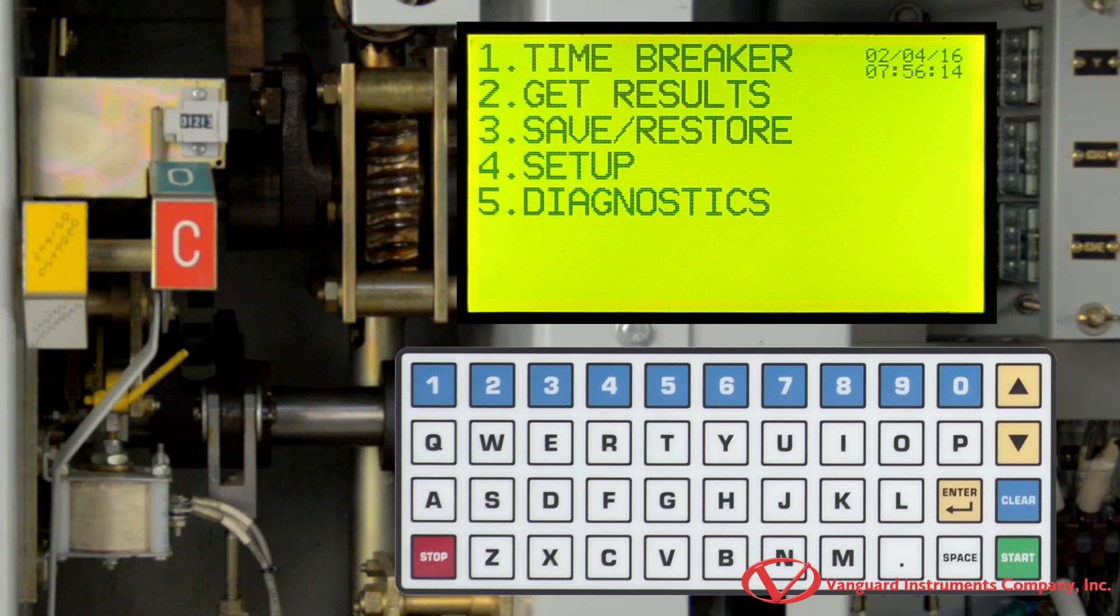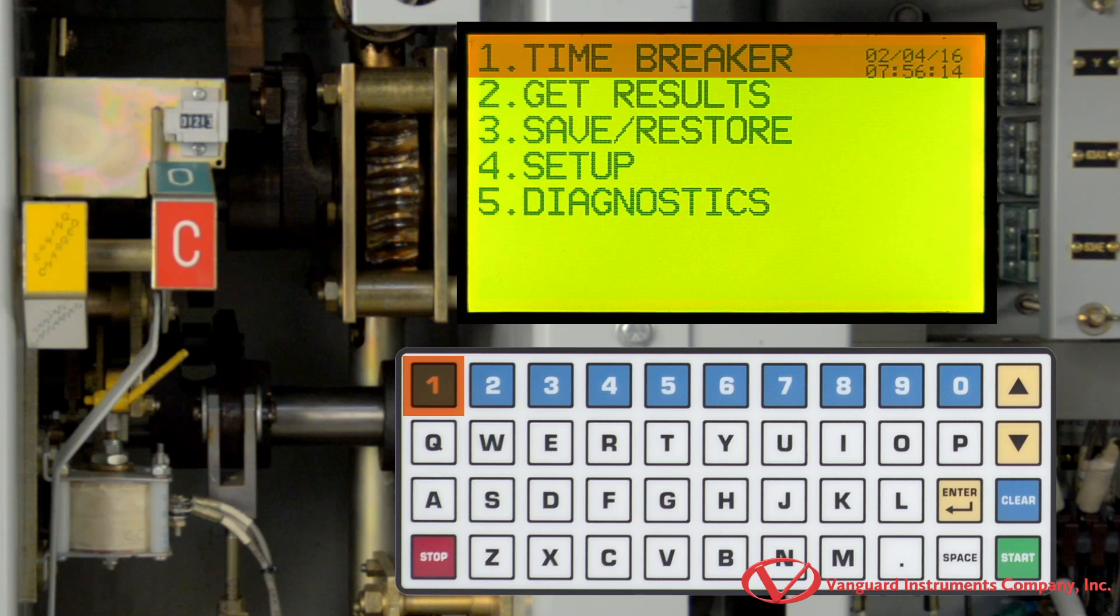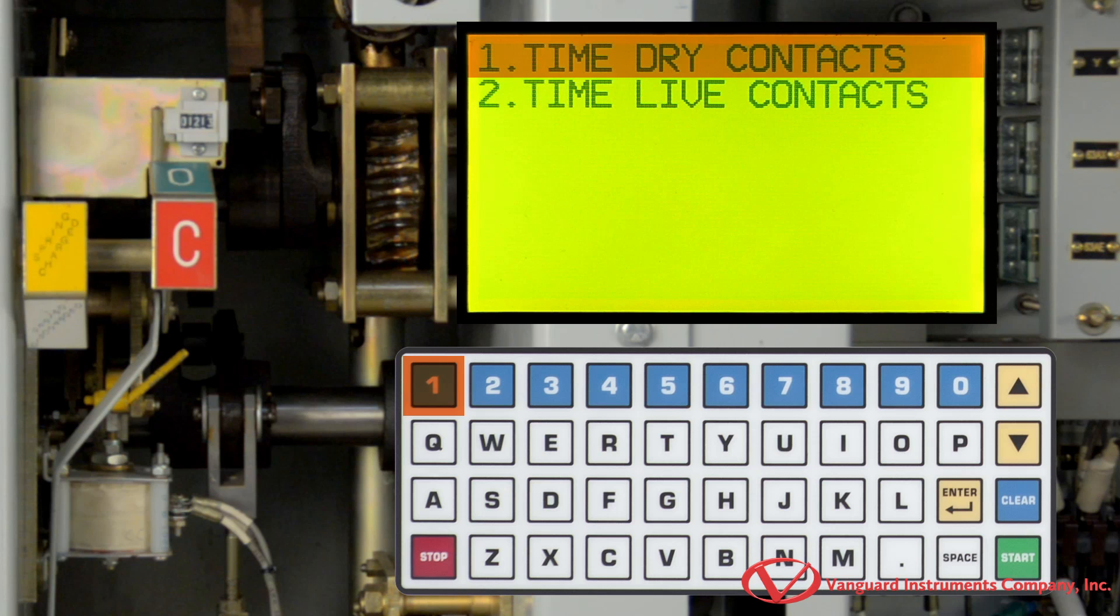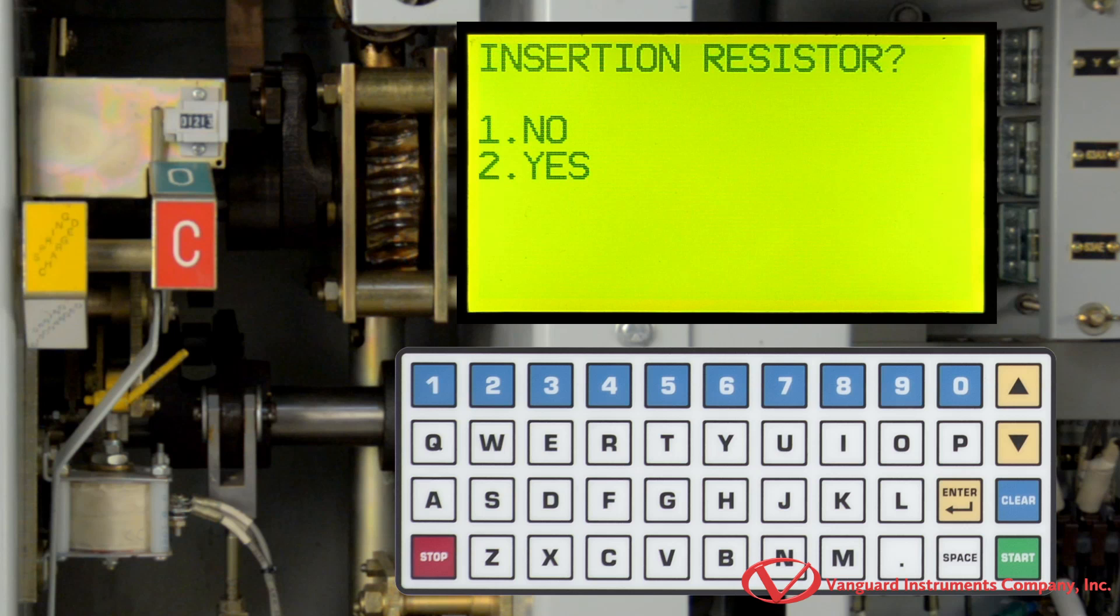To start performing a dual ground test, we will select the time breaker option by pressing the 1 key. Now, we will press the 1 key to select time dry contacts. On this screen, we are going to select whether there is an insertion resistor or not, and for this example, we will press 1 for no.